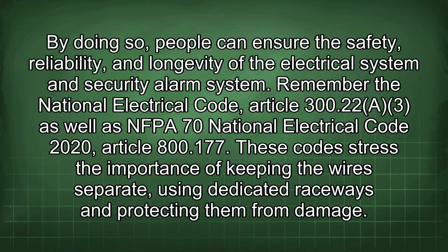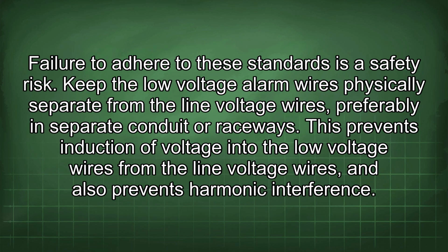Remember the National Electrical Code, Article 300.22 as well as NFPA 70 National Electrical Code 2020, Article 800.177. These codes stress the importance of keeping the wires separate, using dedicated raceways and protecting them from damage. Failure to adhere to these standards is a safety risk.